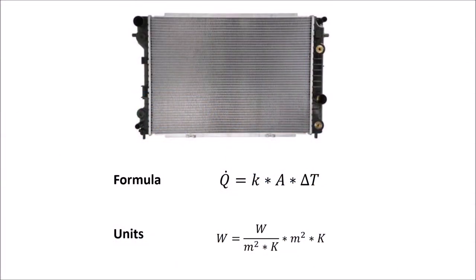In radiator development, there is one important formula: Q̇ = k × A × ΔT. This effectively says that the heat flow is the k factor times the area of the radiator times the temperature difference.